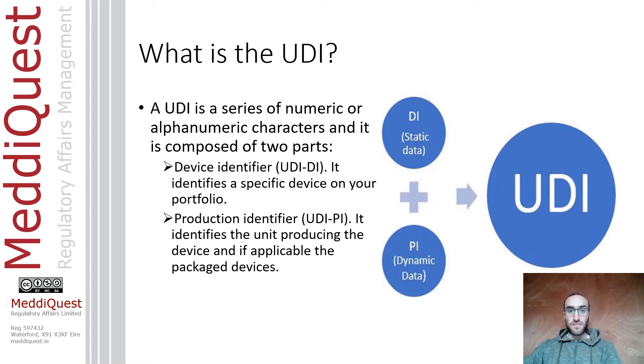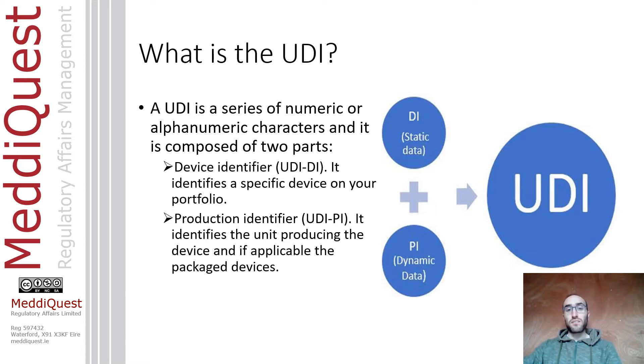Each medical device, and as applicable each package, will have a UDI, which is a series of numeric or alphanumeric characters. It is composed of two parts: the Device Identifier (DI), which identifies a specific device in your portfolio and is the static part that doesn't change within the same model, and the Production Identifier (PI), which identifies the unit of production and includes lot number, serial number, manufacturing date, etc.